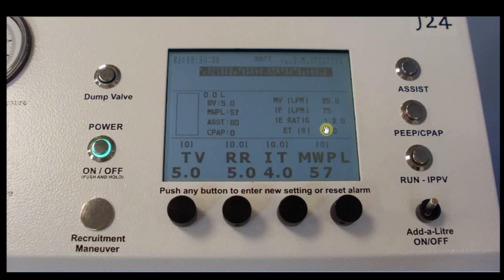These values are resultant values, and these are automatically calculated and updated immediately. So changing any one of these knob values will change the values that are shown up here. At the bottom we have 4 major knobs and their associated values. We have 1 tidal volume, 2 respiratory rate, 3 IT inspiratory time, and 4 MWPL, as we've seen, maximum working pressure limit. At the moment tidal volume is set to 5. This can be set to anything between 0.1 and 20. The respiratory rate is set at 5, can be set anything between 0.5 and 30, I believe. And inspiratory time, anything between 4 and down to 0.5. MWPL up to 80 and down to 5, I believe.